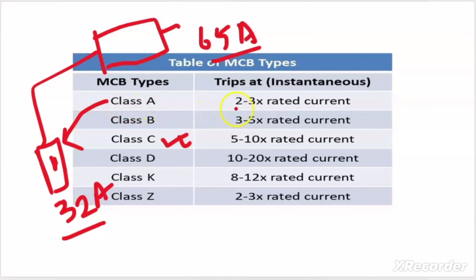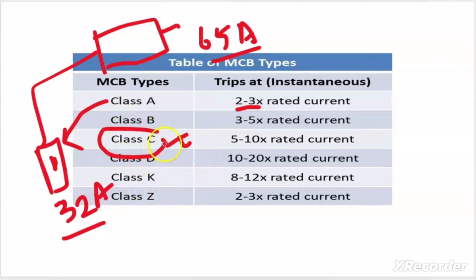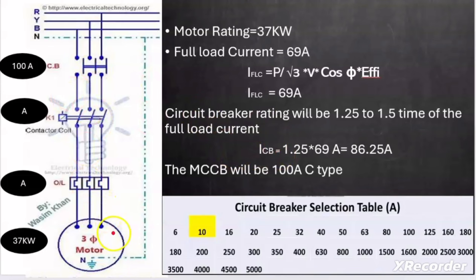Class A type holds current up to 2 to 3 times its rated current, class B type 3 to 5 times, class C type 5 to 10 times, class D type 10 to 20 times, class K type 8 to 12 times, and class Z type 2 to 3 times. For inductive loads it is recommended to use class C type, because an induction motor takes around 8 times the full load current at starting. Since our example motor is an induction motor, I selected C type for the MCCB.